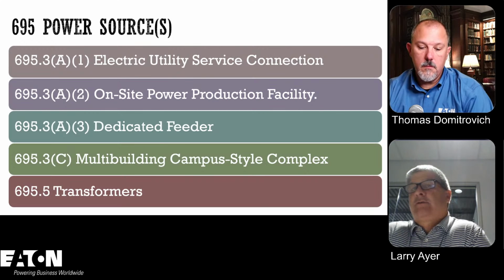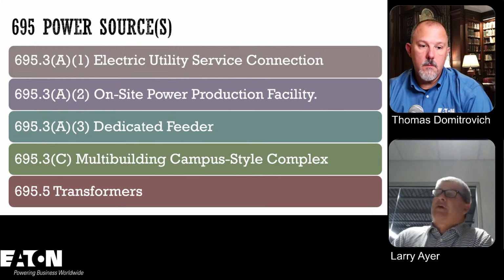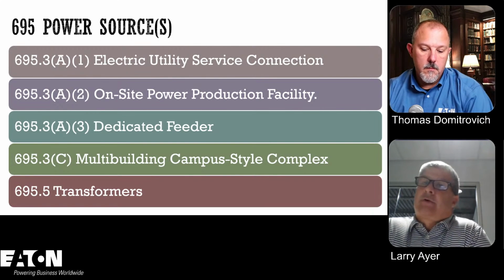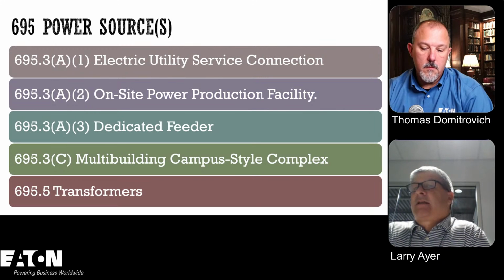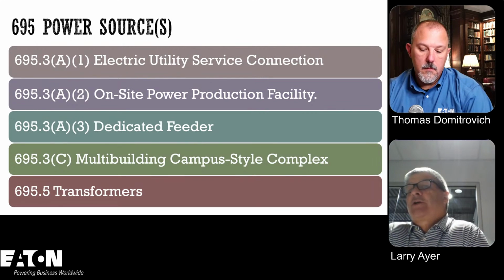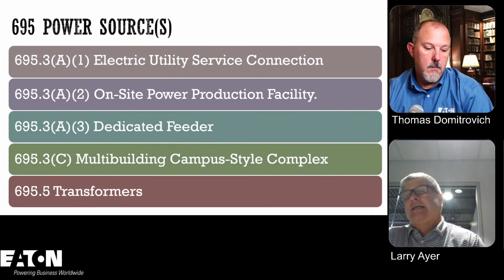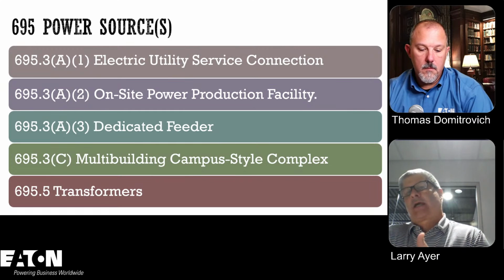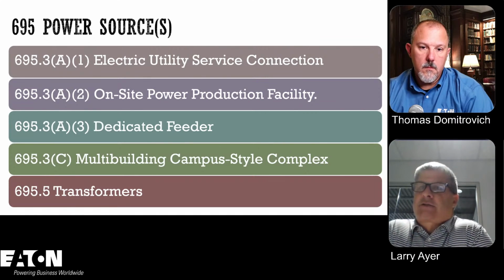Number 2, A2, is your on-site power production facility. So that's your diesel engine-driven fire pump. And number 3 there, A3, is a dedicated feeder. And that A3 is really where you tap off the service in the separate compartment, put a disconnect, and then head to your fire pump controller. But then you kind of switch to 3C and talk about multi-building campus style complexes. And then you skip to 695.5, which is transformers, if you put a transformer in that circuit.